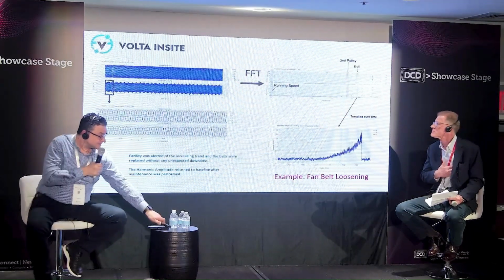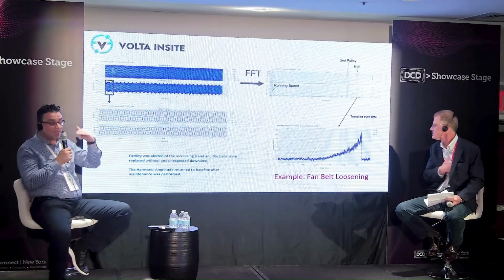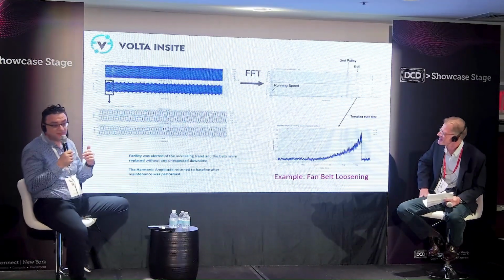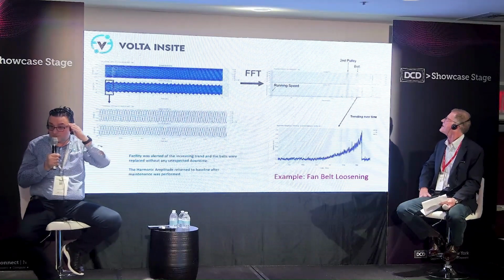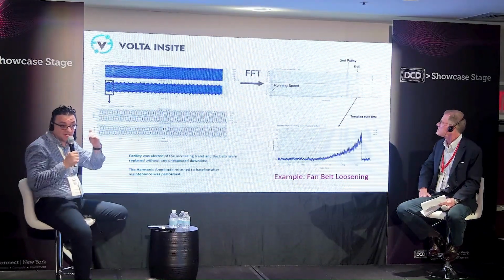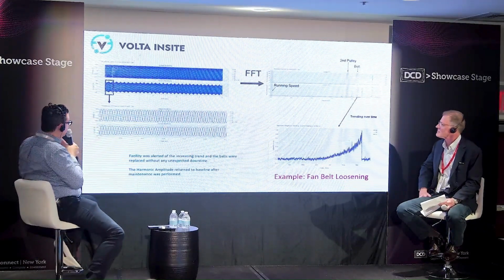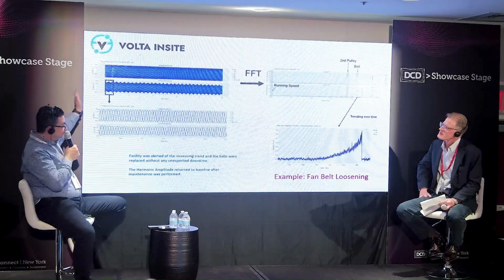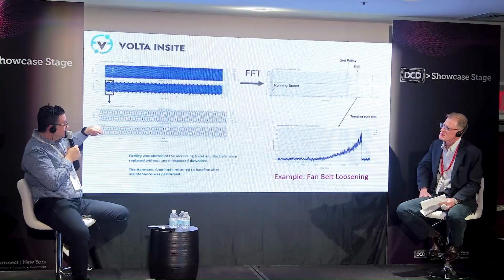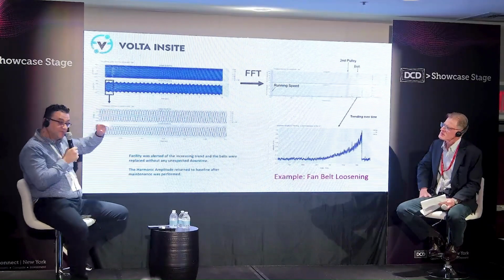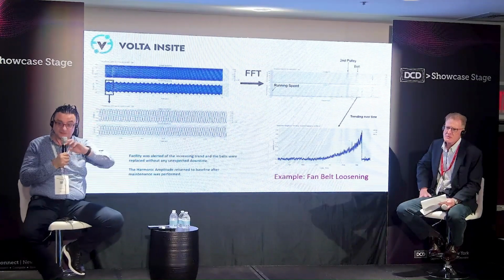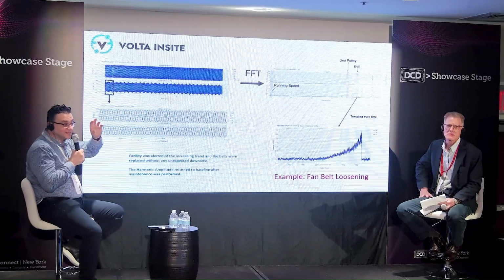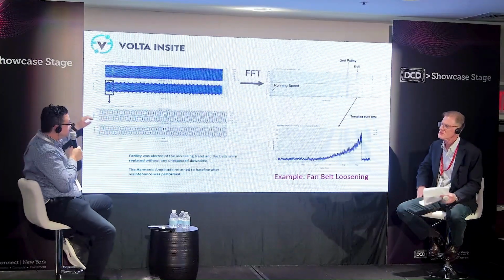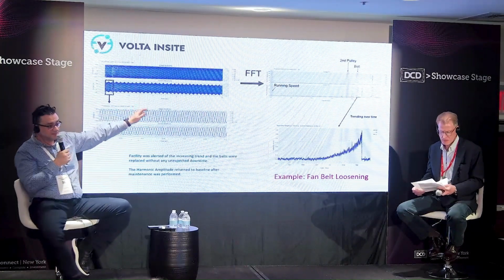That's the basic premise of electrical signature analysis. Now, what that gives us is the ability to go and look at electromechanical equipment. This is more for the infrastructure, operation, and generation side, in that if you're doing this continuous waveform capture, you can take the current, look at your specific load, and look at any type of electromechanical degradation, and map that into the harmonic spectrum.